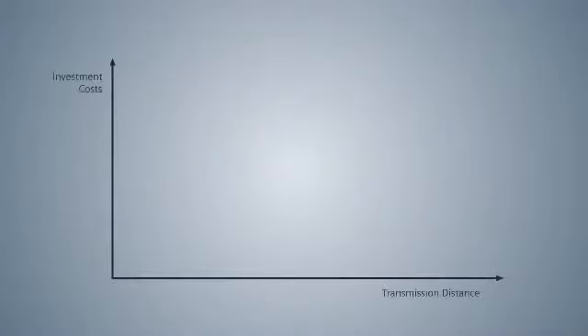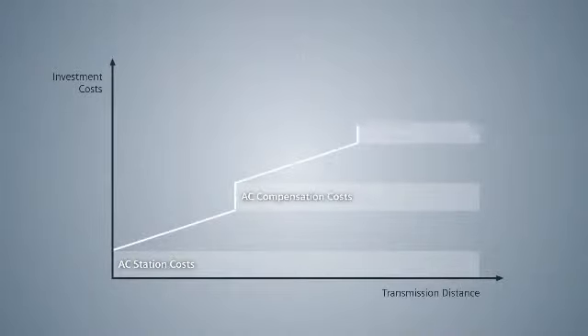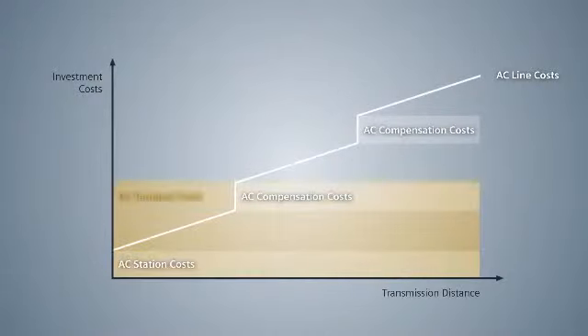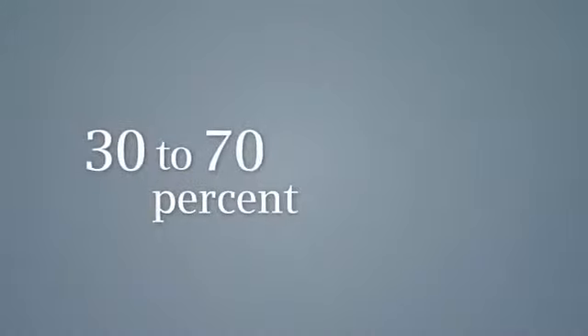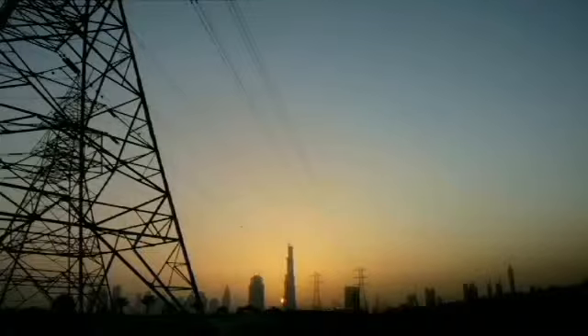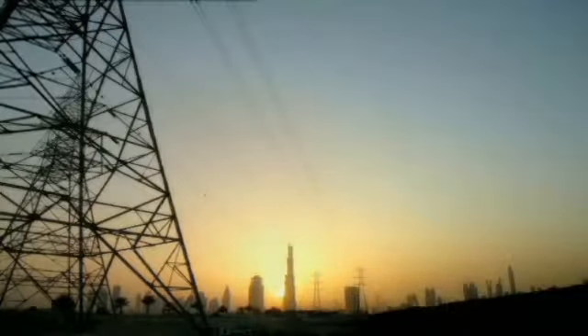AC transmission requires a comparatively low investment at first sight. However, further investments for reactive power compensation and control are required for HVAC transmission over longer distances. HVDC systems involve a higher initial investment for the DC terminals, but do not require additional devices for long-distance transmission. So, long DC lines actually become less expensive than AC lines. Depending on the voltage level, savings of 30 to 70% can be achieved when compared to AC lines. As a result, HVDC technology is especially favorable for long-distance transmission applications.